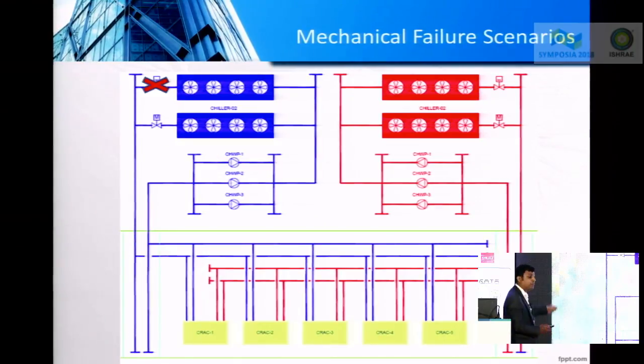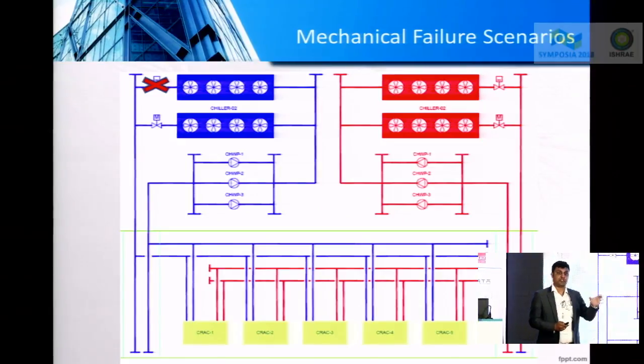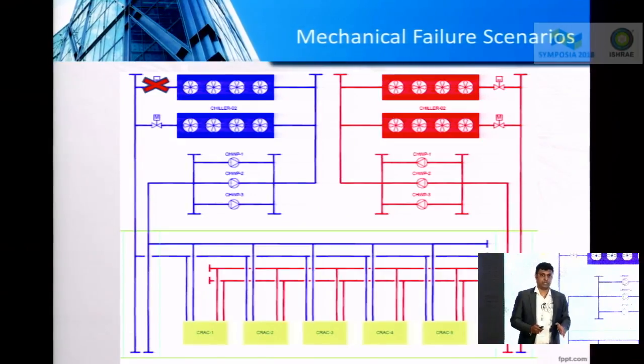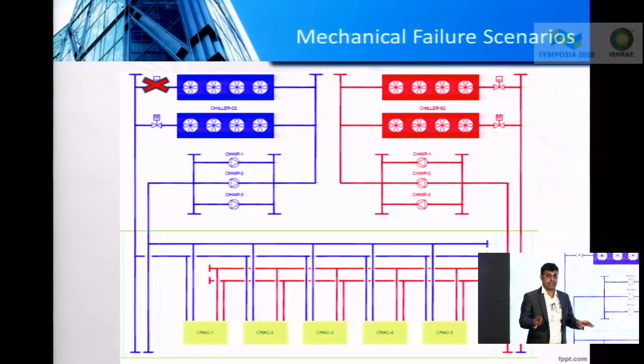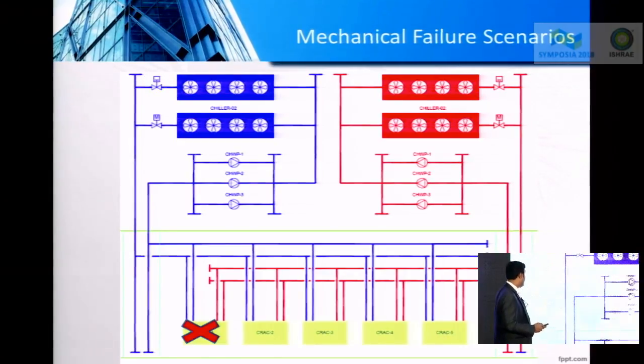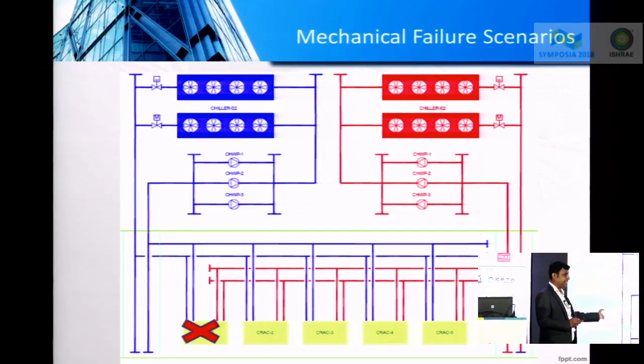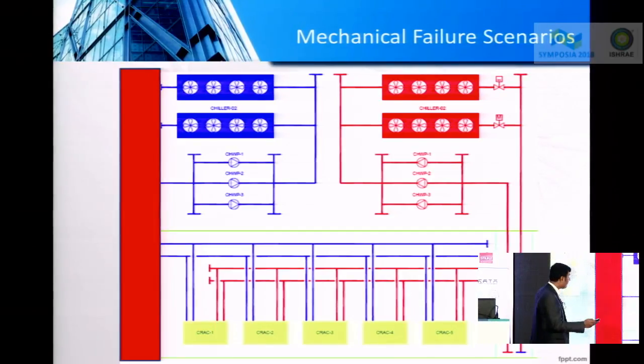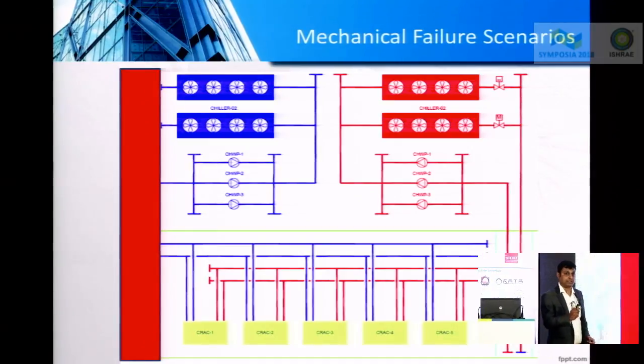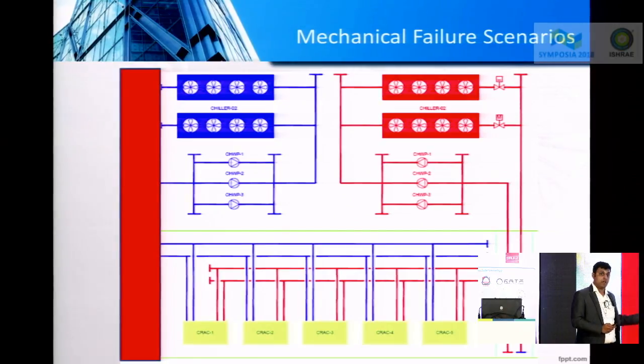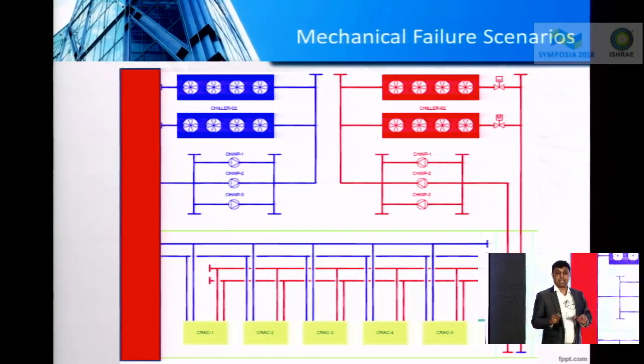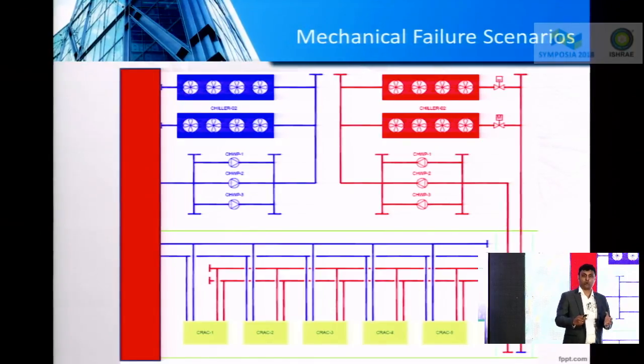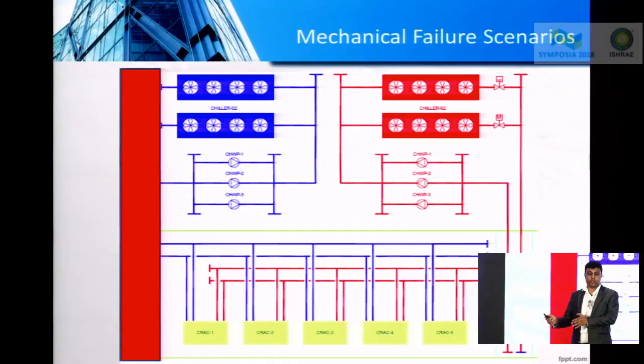I could fail the motorized valve. And once the motorized valve fails, your chiller fails. So it is important that the second chiller comes into the picture, ensuring that there is still no rise in your chill water temperature. I could fail a duty CRAC unit and see if the standby CRAC units come into the picture. I could even fail the entire source A riser, which is the complete loss of source A, and see a transition from source A to source B without any impact on your data hall temperature. So I'm trying to simulate as many scenarios as possible to identify what could go wrong, and still there is no impact on your data hall.